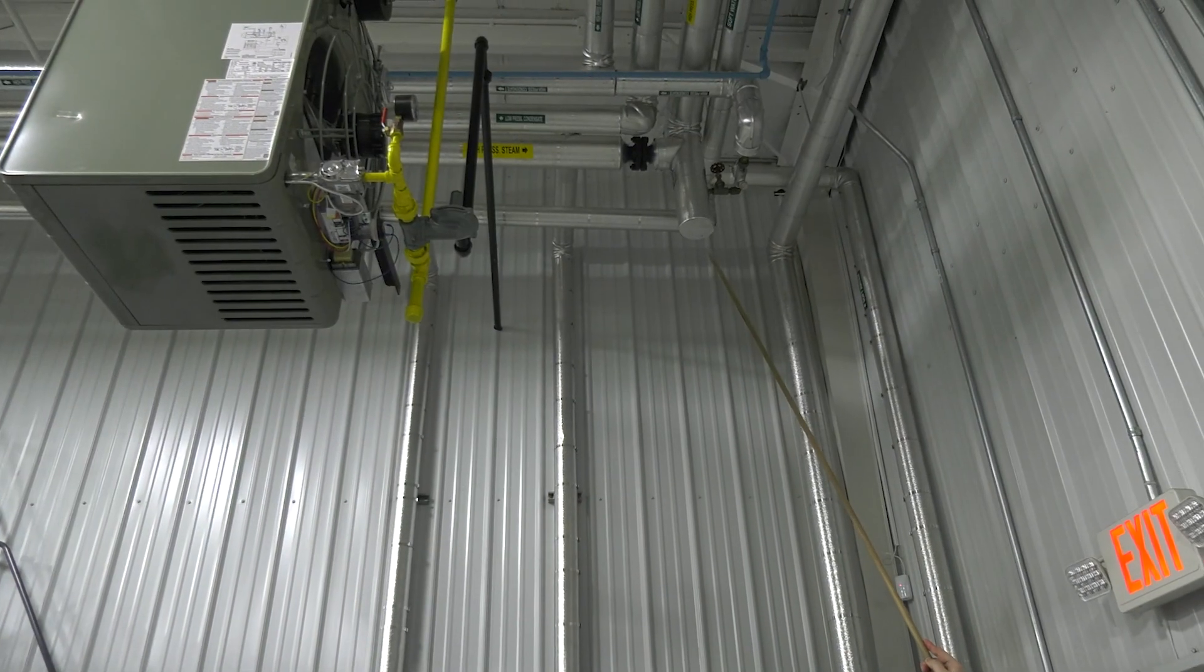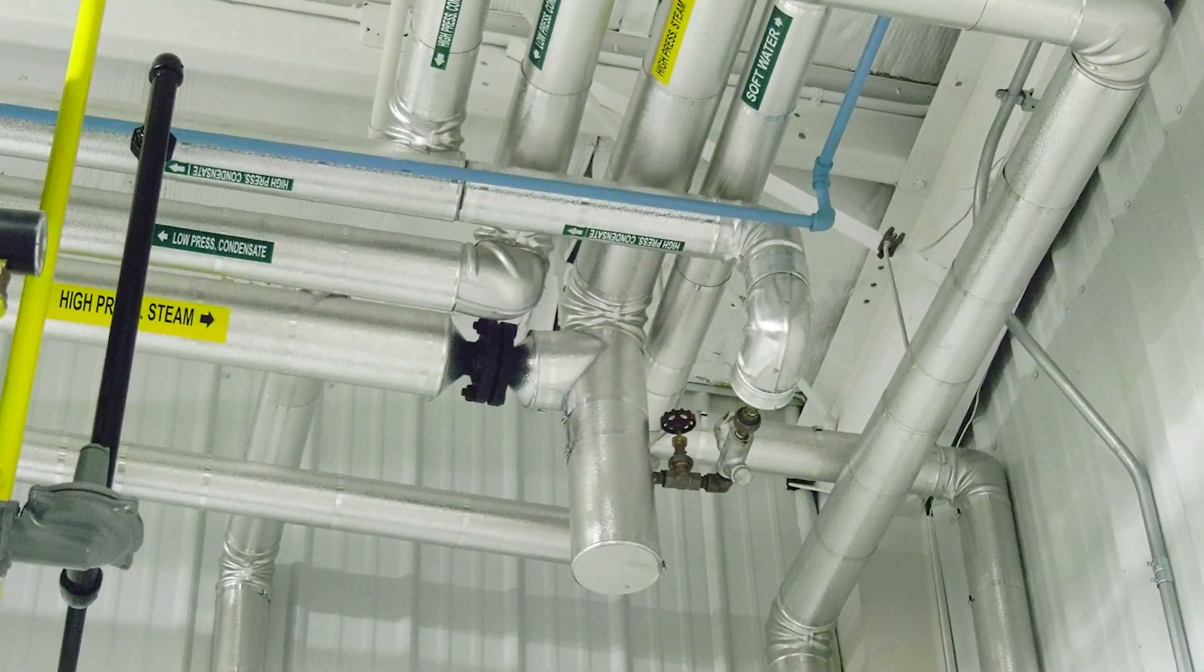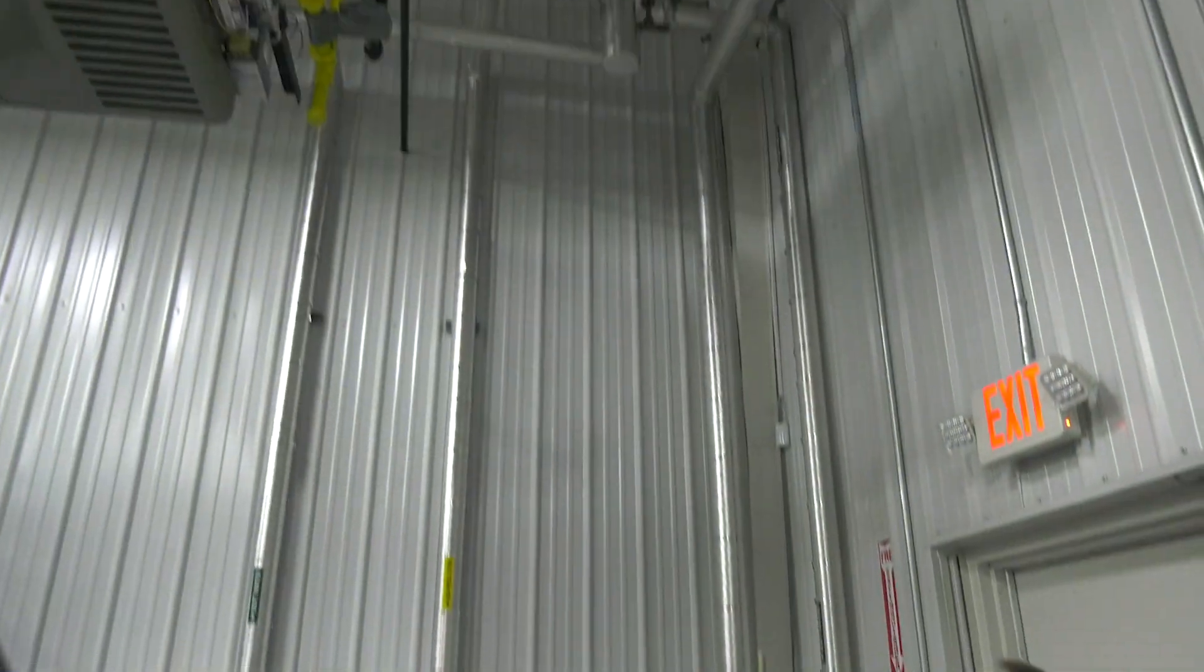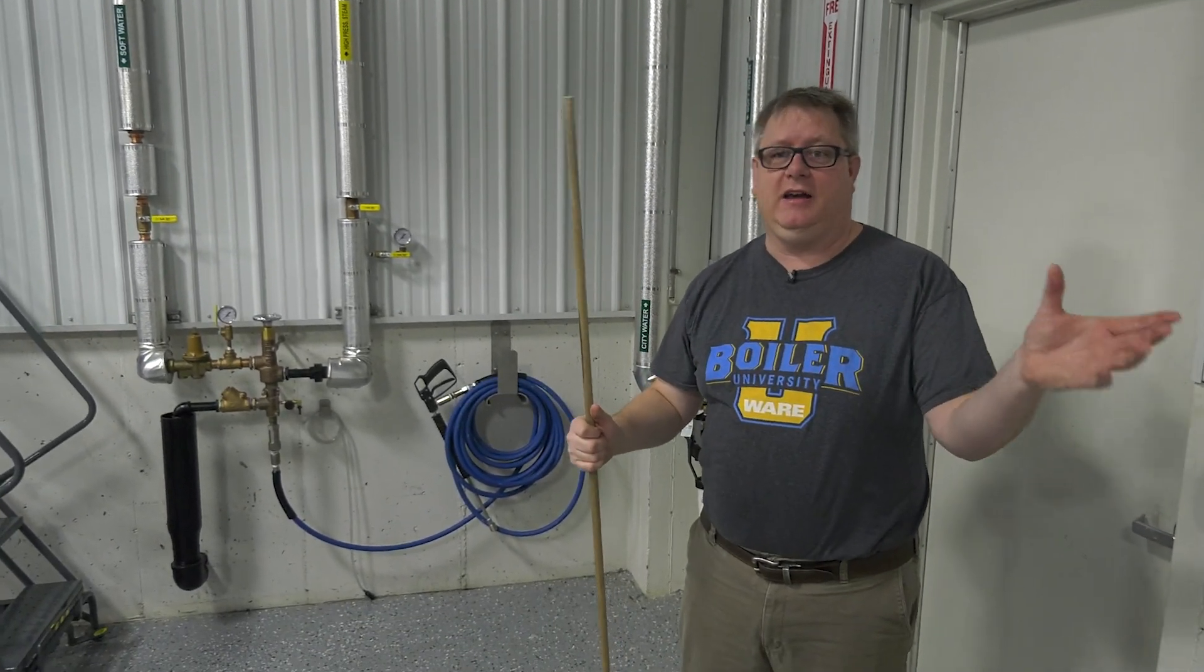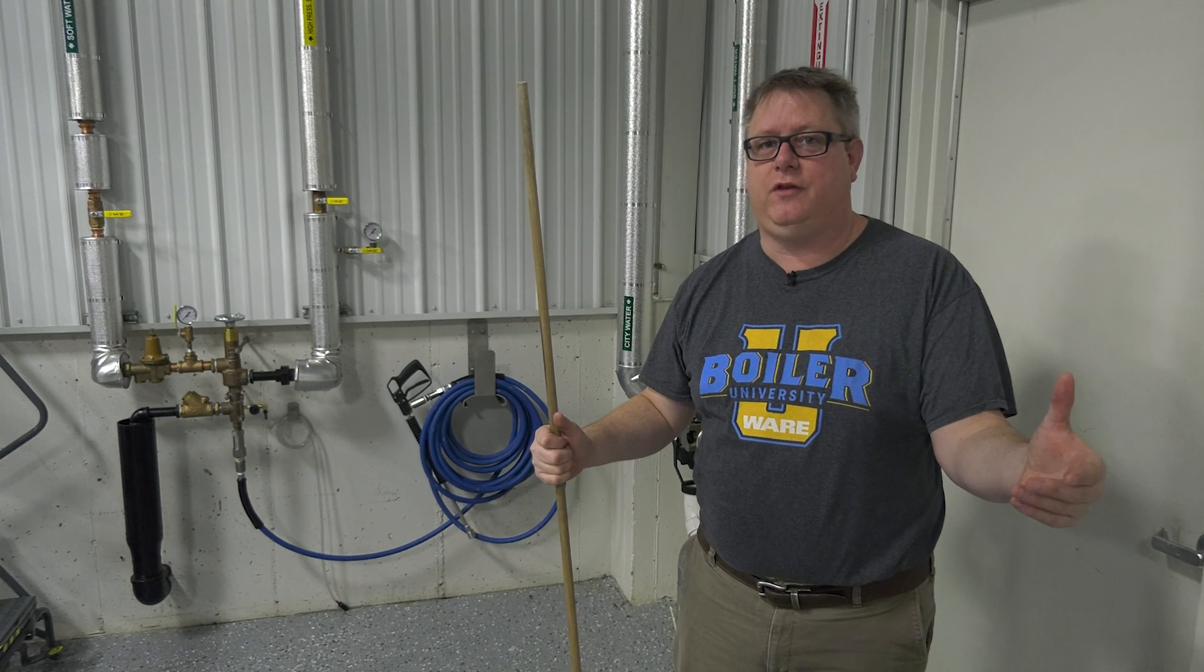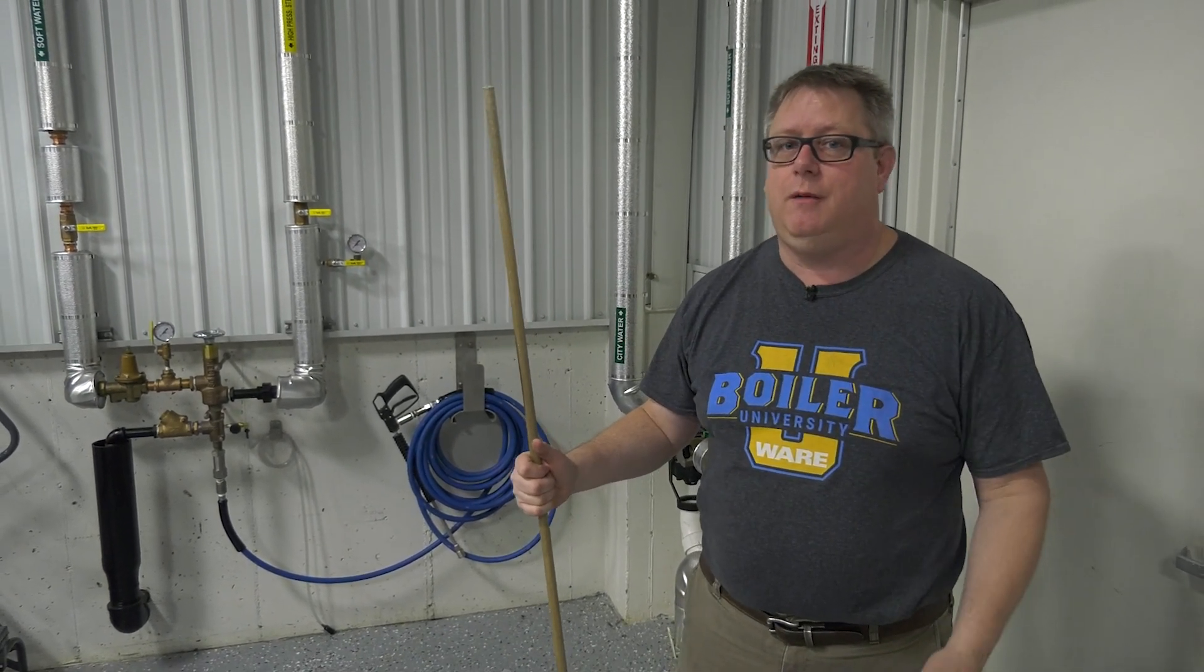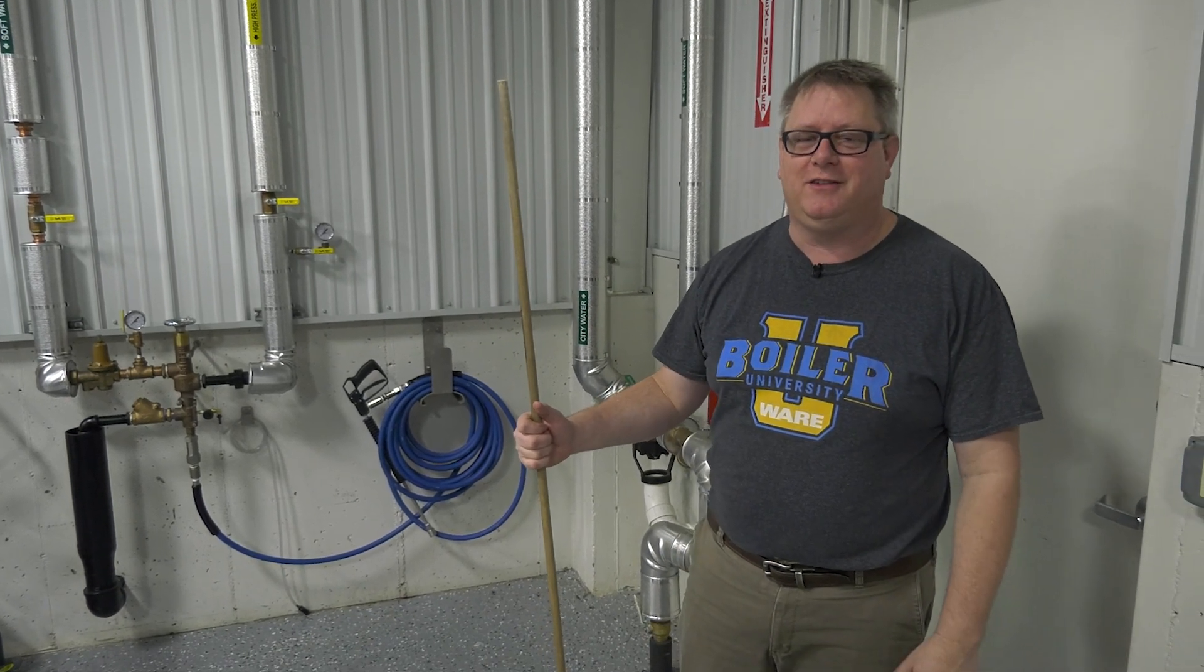And we definitely want to have a drip leg anywhere we elevate our steam line. You can see the steam line just hops up a few inches before going over, but that's definitely going to accumulate condensate there. So anytime we find condensate a problem in our system, there's probably a drip leg that should be there to help keep that clear and make our steam mission successful.